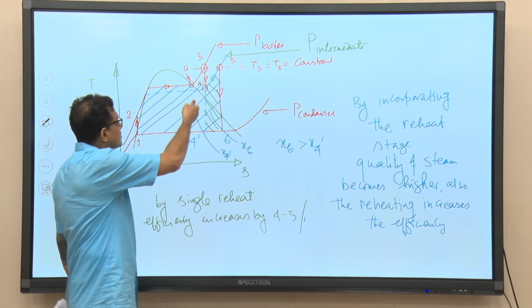Why? Maybe we can go up to 3, 4 or 5 reheat stages, but the gain in efficiency even after having 4 or 5 reheat stages will not be justified by the cost associated with the incorporation of 5 reheat stages. Try to understand. We can go up to 5 or 6 reheat stages, there is no restriction, but the gain in efficiency out of these 6 reheat stages should be justified from the perspective of cost analysis and cost comparison. The cost associated with incorporating 6 reheat stages should be justified by the gain in efficiency that we are getting.